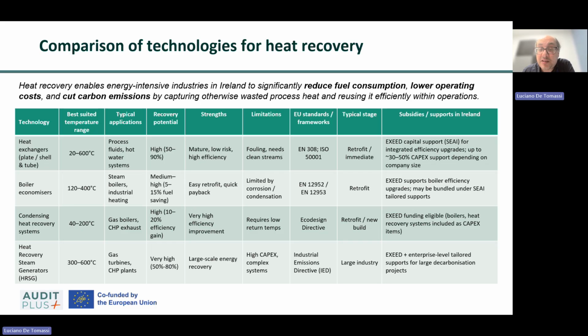Condensing heat recovery systems recover both sensible and latent heat from exhaust gases, making them particularly effective when return water temperatures are below approximately 55 degrees Celsius. They are commonly applied in gas-fired heating systems, district heating networks, hotels, hospitals, and commercial buildings. These systems can achieve an additional 10% to 20% energy recovery compared with conventional heat recovery approaches. Their main advantage is the ability to capture latent heat from water vapor and flue gases, significantly improving overall efficiency. Their effectiveness decreases where return temperatures are high and condensate handling systems are required. They are fully commercialized and supported through standard SEAI energy efficiency grant programs.